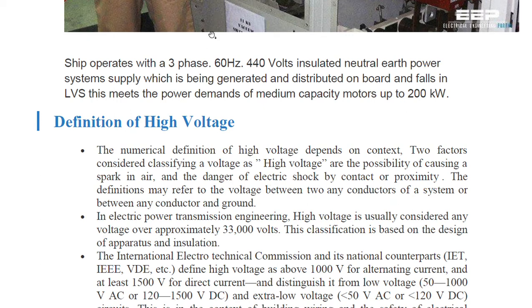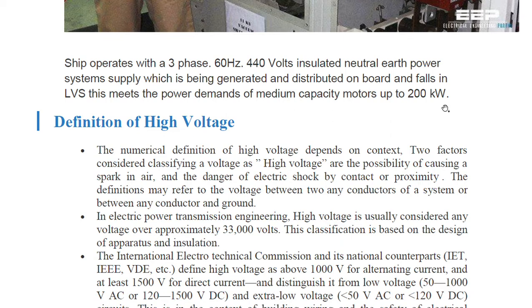Ships typically operate with a three-phase, 60 Hz, 440 volt insulated neutral earth power system supply, which is generated and distributed on board. This falls in the low voltage system and meets the power demand of medium capacity motors up to 200 kilowatt. This is the general trend.